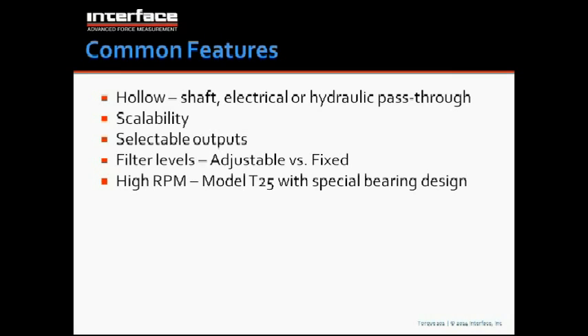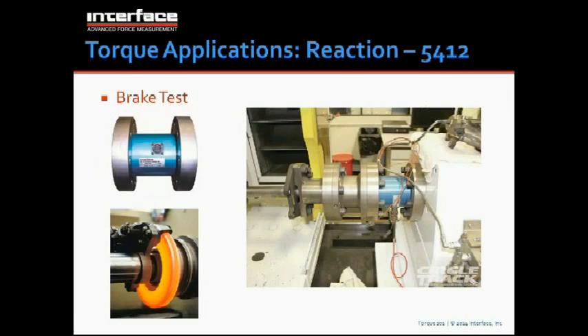There are also some sensors that allow quite high RPM. One example of that is our Model T25, which has a special bearing design, which basically shunts all the bearing friction over to the drive side and removes the bearing friction from the measurement, and also allows for higher rotary speeds. Got some torque examples of applications.